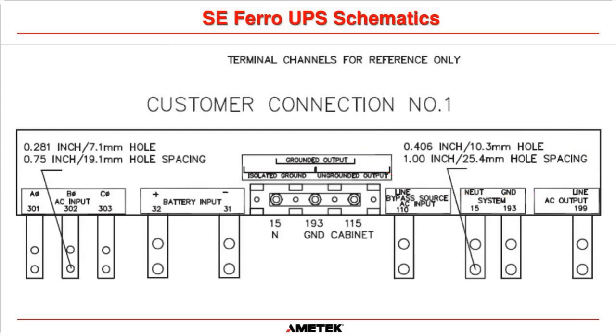Now, I mentioned that we were going to talk about the grounded output connector, so we'll do that here. And this confuses a lot of people, because what you get is you get 2 bus bars shipped with the system. Now, obviously, we don't know if you've got a high resistance ground network, if you're putting this on a ship and there's no ground. We don't know what you're doing with your ground circuit. So we have to give you the ability to connect your system in many different ways. But the easiest thing to remember is this terminal is connected to the neutral. So basically, it's connected over to this neutral here inside the system.